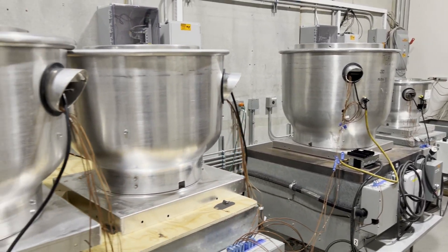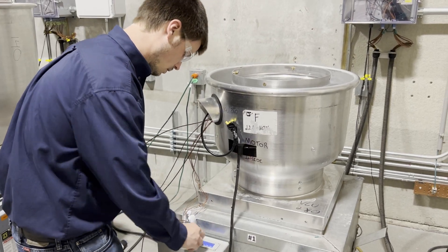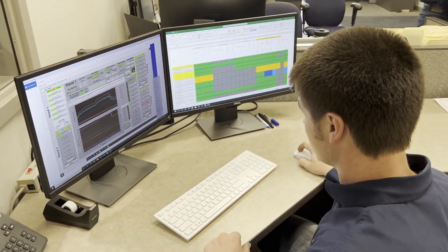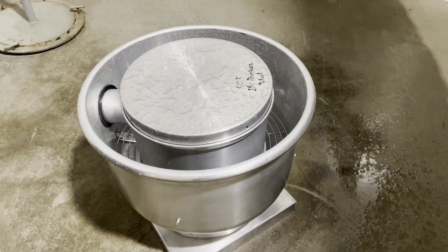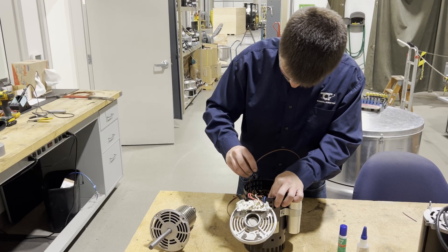On powered roof ventilators, it's not uncommon to have motors fail because of lack of grease or other mechanical issues. It's less common, thanks to UL testing and UL listings, that those failures are due to fires, short circuits, or breakdown of the electrical components within the motor itself. The purpose of our UL lab is to mitigate that risk. We subject them to a variety of tests as laid out by UL — giving them a wide variation of voltage, including low voltage which increases amperage and leads to higher heat within the motor. It's essentially a torture test on the motor to make sure that under any condition it will survive and function as intended.